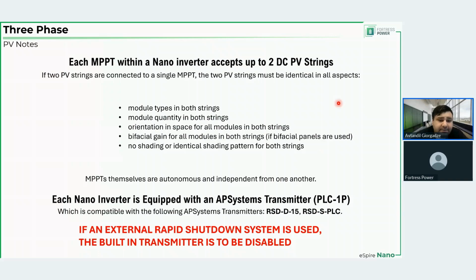And the AP Systems transmitter that I was talking about, this is the model of it, PLC-1P, and it is fully compatible with RSD-D15 and RSD-SPLC. This is very important. If an external rapid shutdown system is used, the built-in transmitter is to be disabled. Let's say you want to have TIGO optimizers. So you need to introduce a TIGO system to the PV array, right? You cannot have both TIGO and the APS transmitters in place. So you will disable the APS transmitter and enable the TIGO transmitter. And we will provide, in one of the appendices of the inverter manual, instructions on the proper way of doing it.